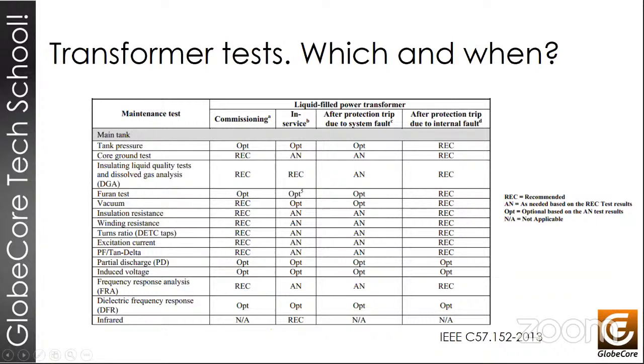Vacuum is a very important thing when commissioning a transformer, but it's not required for maintenance usually, and also unnecessary for external faults. Now that an internal malfunction occurs and we think we're going to repair the transformer, we'll most likely need vacuum purification for this. Next slide, please.